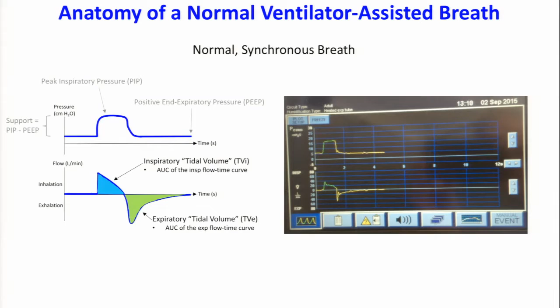So we can actually derive a tremendous amount of information from this, as I said. So we can have discrete data fields like the peak inspiratory pressure that gives us a sense for how much maximum push is going into the patient. We actually regulate the pressure on the way out to keep lung units from collapsing at the end of exhalation. We call that positive end expiratory pressure. And then we can look at the difference between those as the driving force that's providing help to the patient. We can then take the flow time curve and do simple things like integrate the area under that curve. Because this is a liter per minute at each instantaneous time point, the integral of that ends up yielding the inspiratory tidal volume. This is what the ventilator does and shows us these parameters on the user interface of the ventilator.